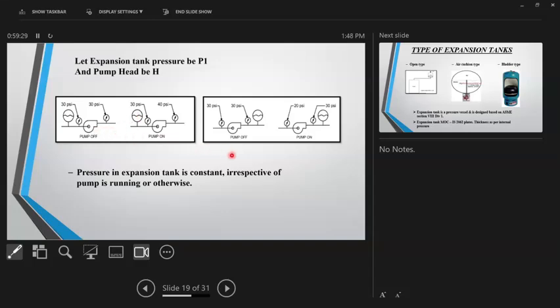Let us take a very, very skewed example, that for some reason you have put the expansion tank on the outlet of the pump. When the pump is not running, obviously no problem. It's all static head, 30 meter head. When you start the pump and the pump head is 10, the pressure over here won't increase. It will still be 30 psi. What would happen is the suction pressure would reduce to 20 psi to make up for that head developed by the pump.